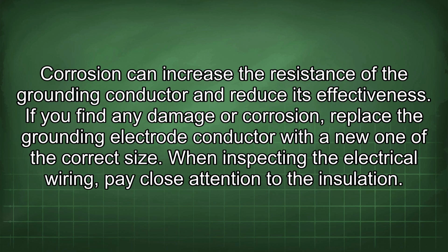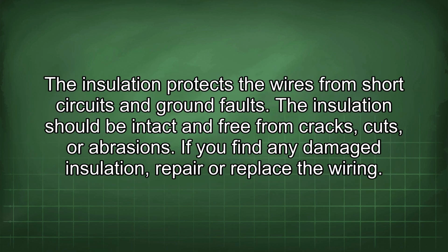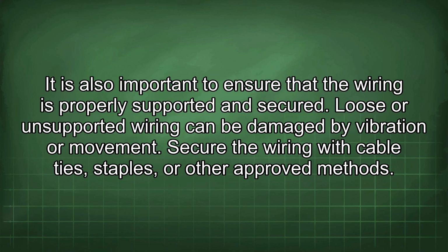When inspecting the electrical wiring, pay close attention to the insulation. The insulation protects the wires from short circuits and ground faults. The insulation should be intact and free from cracks, cuts, or abrasions. If you find any damaged insulation, repair or replace the wiring. It is also important to ensure that the wiring is properly supported and secured. Loose or unsupported wiring can be damaged by vibration or movement. Secure the wiring with cable ties, staples, or other approved methods.